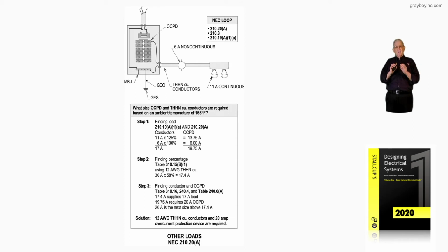And from this calculation, conductors to the left, overcurrent device to the right, telling you what, when I multiply by 125%, I derate the loading of the overcurrent device to 80%, so the conductor comes along at 125%, and sizing the overcurrent device to terminate to the overcurrent device for any load that operates for 3 hours or more is identified as continuous load in Article 100.